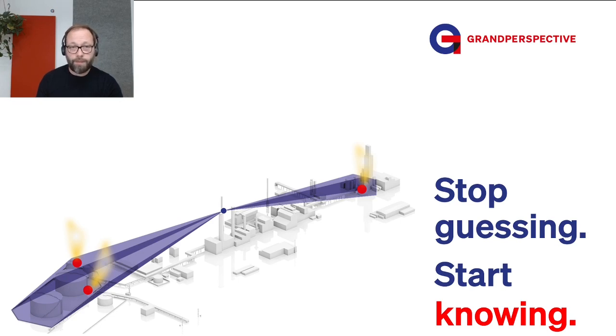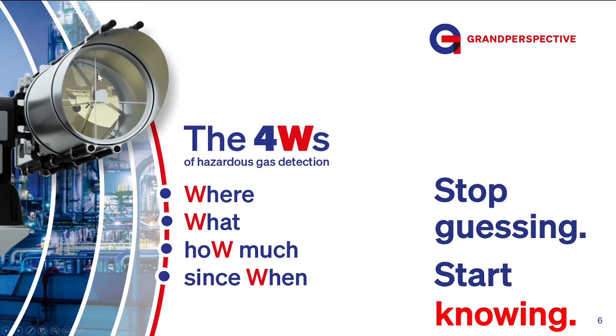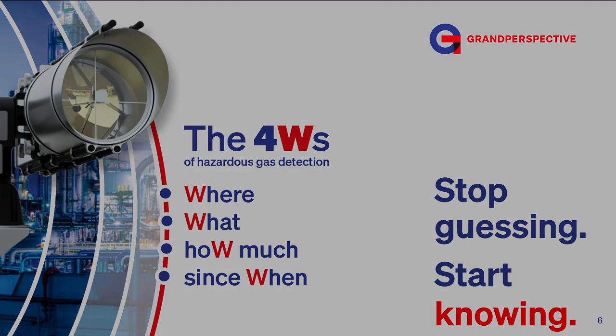And spectroscopy is something that is routinely used in the lab for chemical analysis. Why? Well, chemical analysis is the determination of the chemical composition, and FTIR spectroscopy has the benefit that it can distinguish up to several hundred chemical compounds, sometimes even in mixtures. This technology is now brought by Grand Perspective into the industry, developing a system for an automated 24/7 monitoring of the facility. Basically, this is answering 4 questions. Where is the gas? What is the chemical composition of the gas? How much is there, and since when is this event developing?